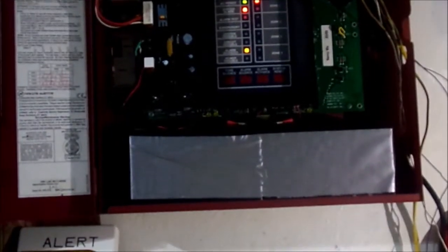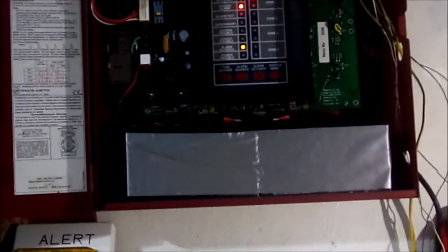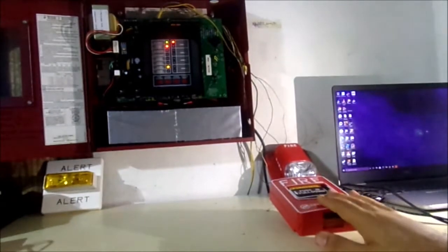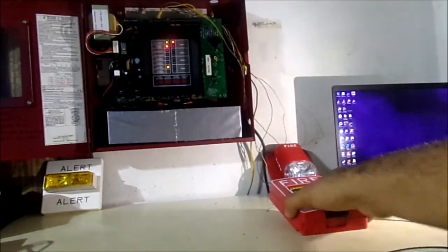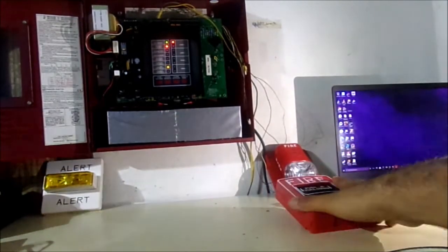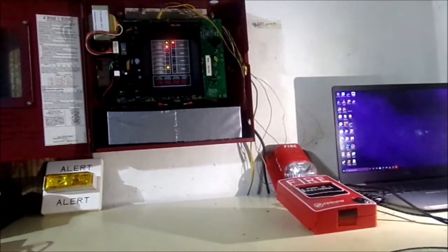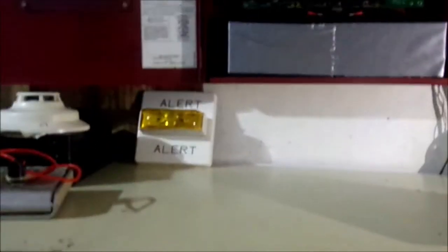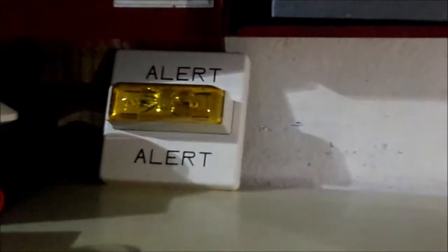And that's how you silence the fire alarm right there. You press tone silence and alarm silence. Now, when the pull station is pulled, you got to make sure it's reset. Otherwise, if you reset the system, it's going to go back to alarm. Now, the focus here is just to test and make sure both of them work. But now we're going to go and focus this on this device here.